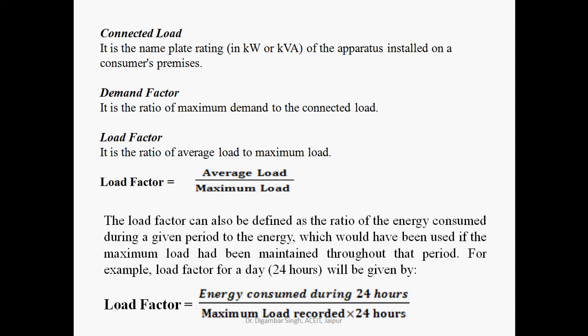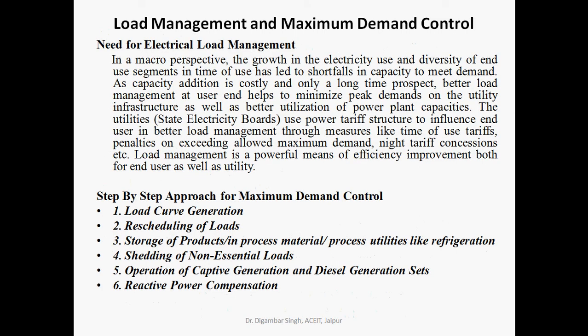Demand factor is the ratio of maximum demand to connected load. Load factor is the ratio of average load to maximum load, also defined as the ratio of energy consumed during a given period to the energy which would have been used if the maximum load had been maintained throughout that period. For example, the load factor for 24 hours is energy consumed during 24 hours divided by maximum demand recorded in 24 hours.